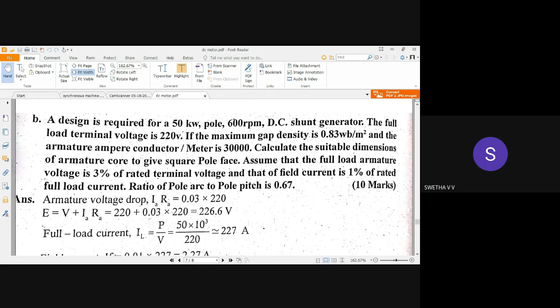The full load terminal voltage is 220 volt. If the maximum gap density is 0.83 Weber per meter square and the armature ampere conductor per meter is 30,000, calculate the suitable dimensions of an armature core to give square pole face. Assume that the full load armature voltage drop is 3% of rated terminal voltage and that the field current is 1% of rated full load current. Ratio of pole arc to pole pitch is 0.67.